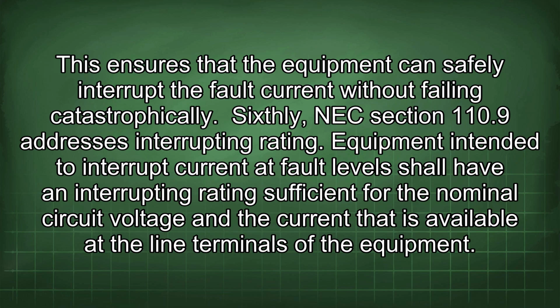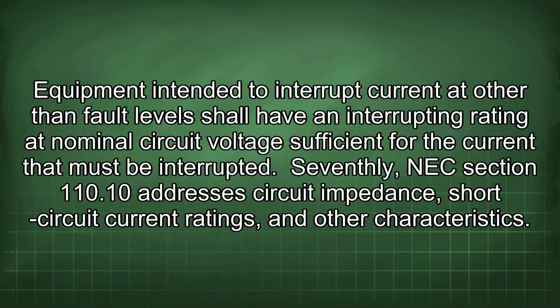Sixthly, NEC section 110.9 addresses interrupting rating. Equipment intended to interrupt current at fault level shall have an interrupting rating sufficient for the nominal circuit voltage and the current that is available at the line terminals of the equipment. Equipment intended to interrupt current at other than fault level shall have an interrupting rating at nominal circuit voltage sufficient for the current that must be interrupted.